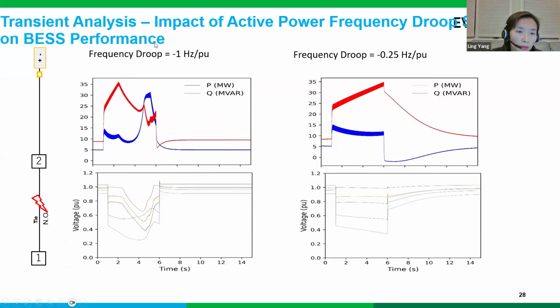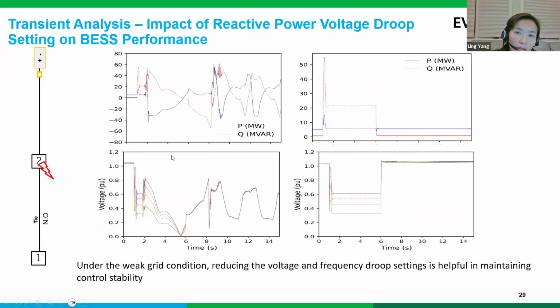This shows the frequency droop settings with different values, and you may notice the system performance is different. On the left are the droop settings in the early stage, and this is the performance after we changed the frequency droop setting. You can notice the differences in system performance between the two settings. Also, the system voltage under fault conditions was all over the place previously, and later on we changed the voltage droop settings to try to slow down the inverter controls. Under weak grid conditions, through our simulations, we found that reducing the voltage and frequency droop settings helps maintain system control and stability.